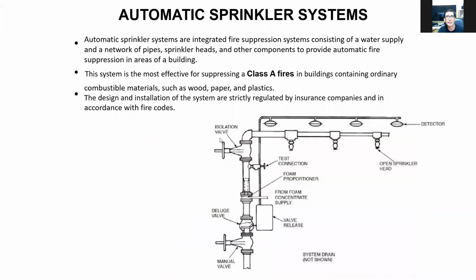Now, we have the automatic sprinkler system. Automatic sprinkler systems are fire suppression systems consisting of a water supply and a network of pipes, sprinkler heads, and other components to provide automatic fire suppression in buildings or areas in buildings. This system is most effective for suppressing a class A fire in buildings containing ordinary combustible material such as wood, paper, and plastics. The design and installation of the system are strictly regulated by insurance companies and in accordance with the fire code. So this fire sprinkler system is combined with a detector system. The detector system will also activate the fire sprinkler system in case there is only smoke, or in case there is heat inside the building.